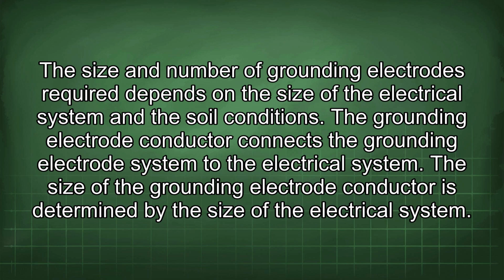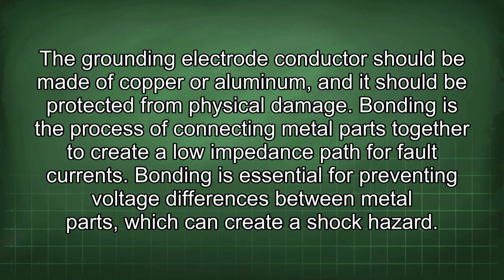The grounding electrode conductor connects the grounding electrode system to the electrical system. The size of the grounding electrode conductor is determined by the size of the electrical system. The grounding electrode conductor should be made of copper or aluminum, and it should be protected from physical damage.